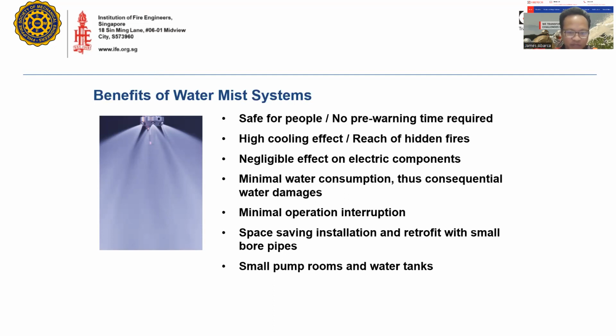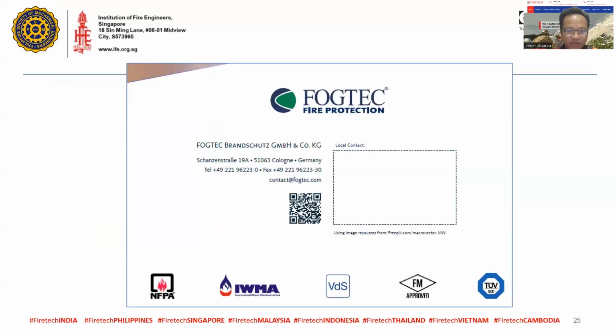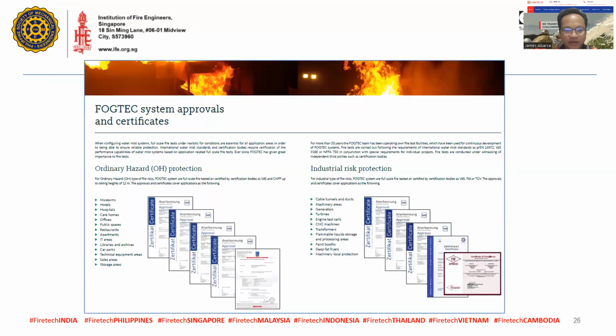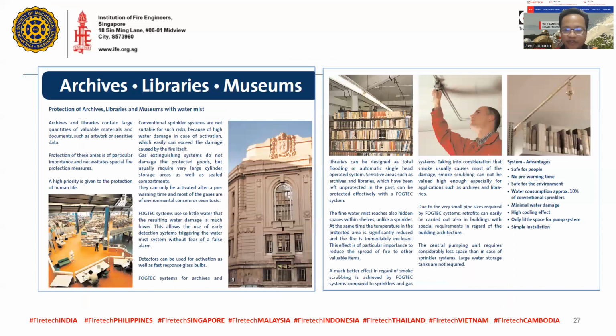One of the big problems in the fire protection system is when they require a very big pump, a very big pump room, and a very big water tank. But for water mist, you will have just less requirement. We are FM approved system. Some more of the applications in the form of a catalog. That's why water mist can be applicable in archives, libraries, and museums.